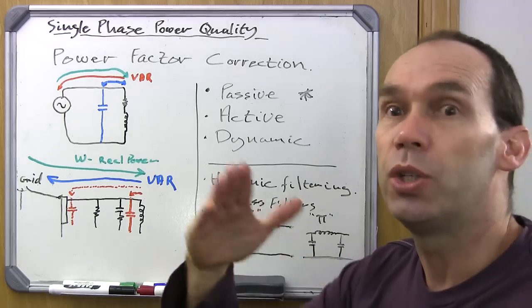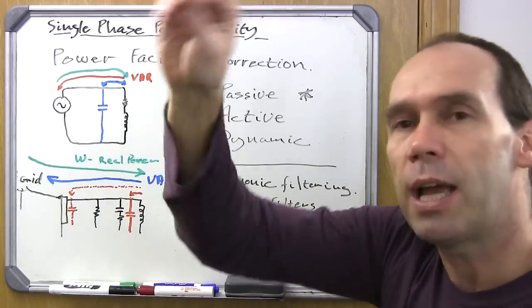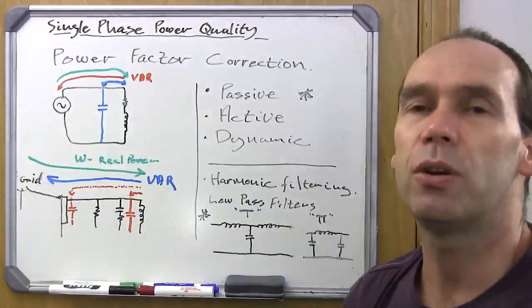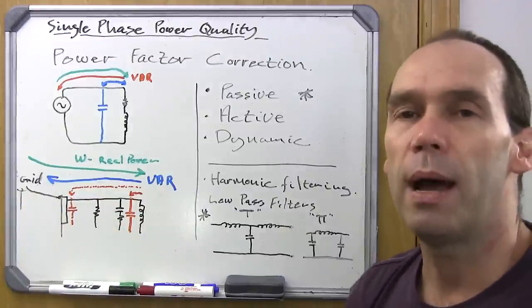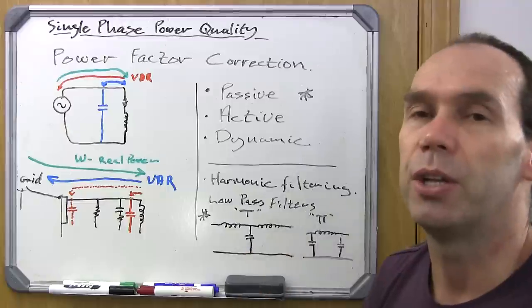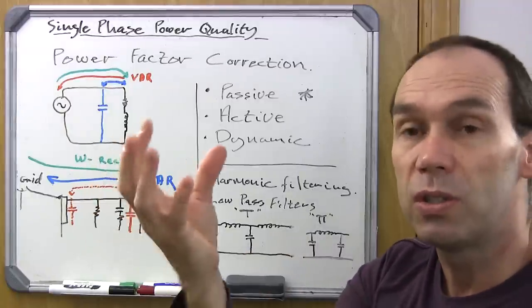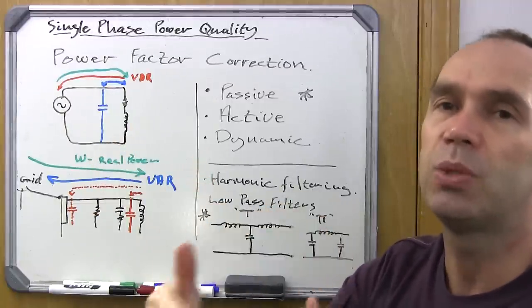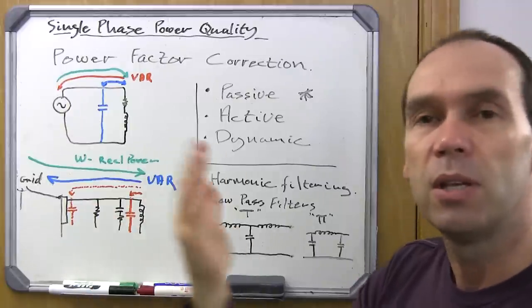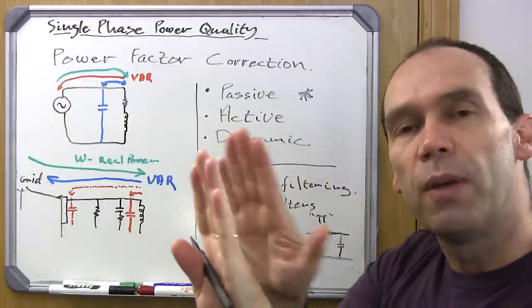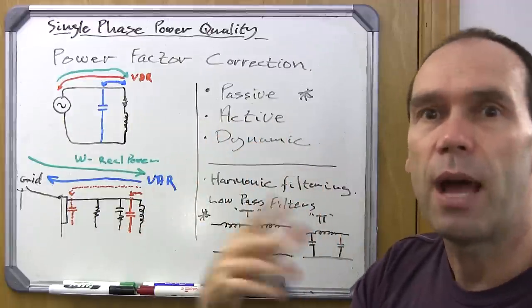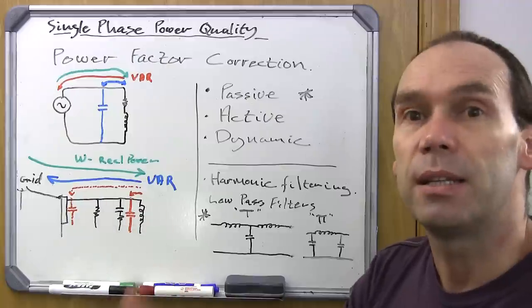If loads are changing fairly quickly, that kind of switching will create too many transients and spikes on your power line. That's when you get to dynamic power factor correction, where solid-state switching is used, which can easily switch in the relevant amount of inductance or capacitance to get voltage and current in phase — and do that without creating transients or upsetting the power line.